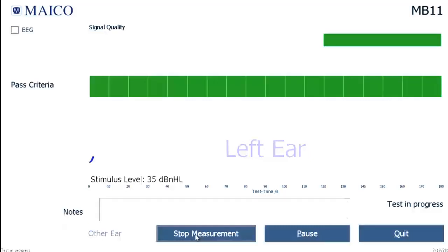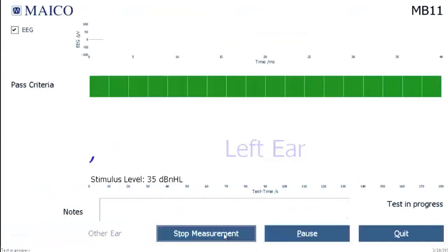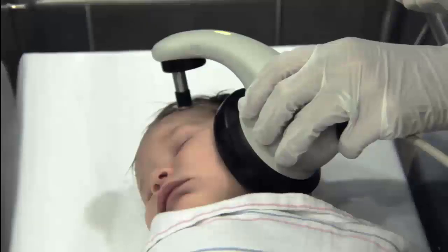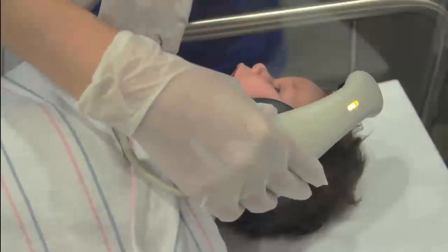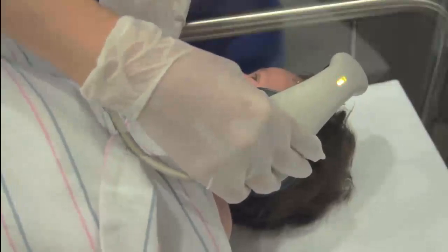Artifacts can also be observed by watching the signal quality feedback at the top of the measurement screen. Under good conditions, the signal quality will display green, but yellow or red if there is interference. If you prefer the alternate EEG view, you will see that under good test conditions, the EEG line will be virtually flat. If there is interference, this line will reflect this activity. Also during the ABR measurement, the LED light on the MB11 hardware will be green when good data samples are occurring, but will flash yellow or red as artifacts occur.